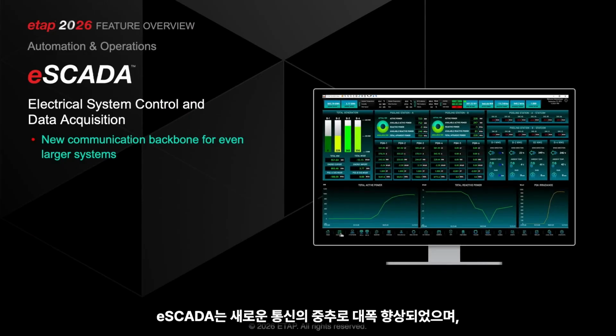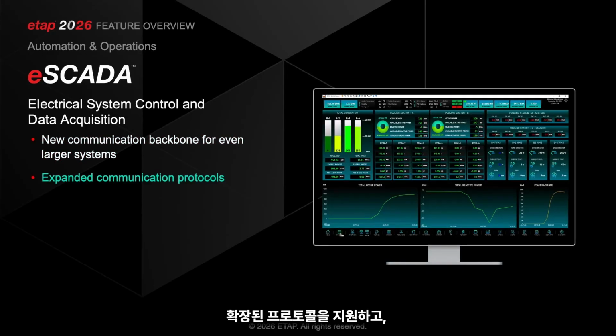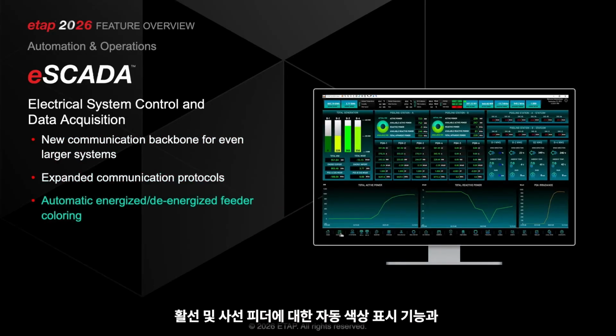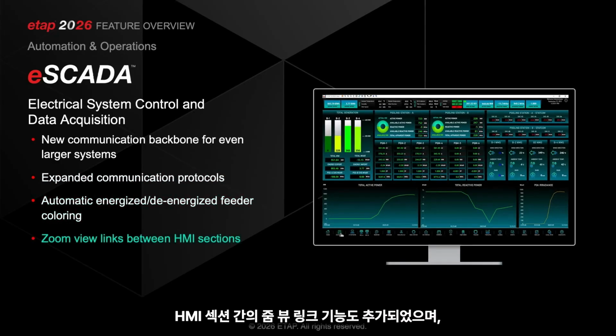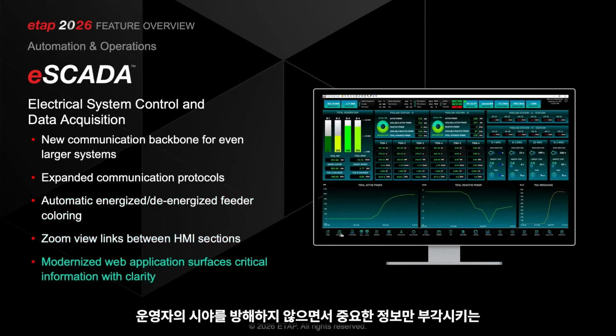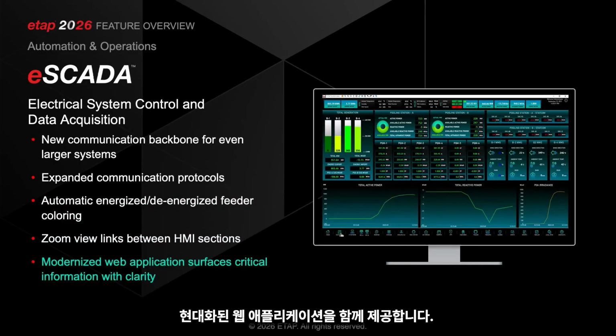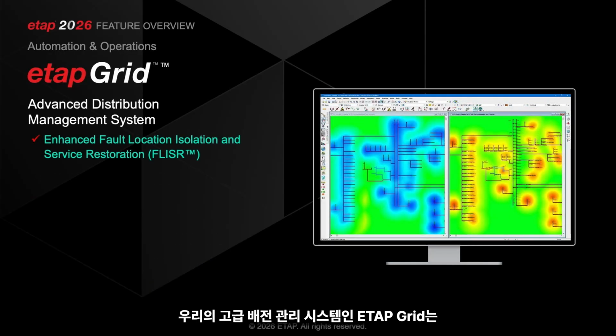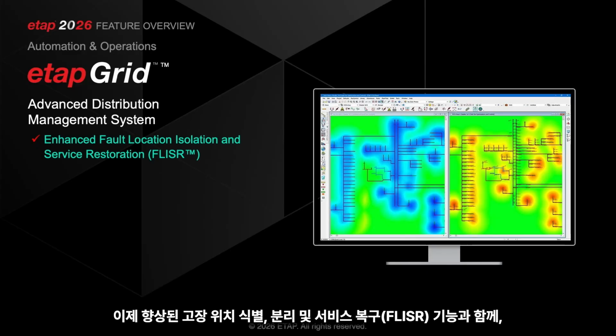eSCADA has been enhanced with a new communication backbone, which improves managing very large systems, expanded protocol support, automatic energized and de-energized feeder coloring, zoom view links between HMI sections, and modernized web applications focused on surfacing critical information without cluttering the operator's view. ETAP Grid, our advanced distribution management system, now delivers enhanced fault location, isolation, and service restoration.